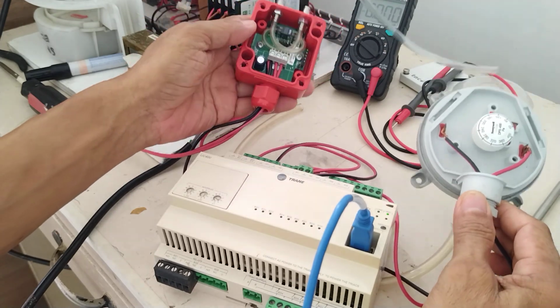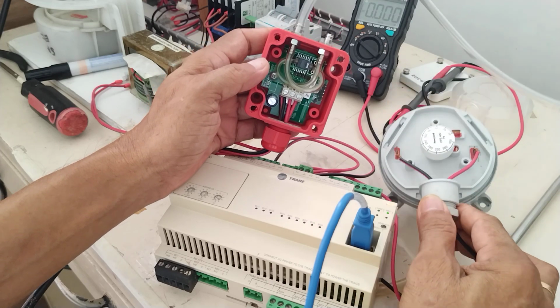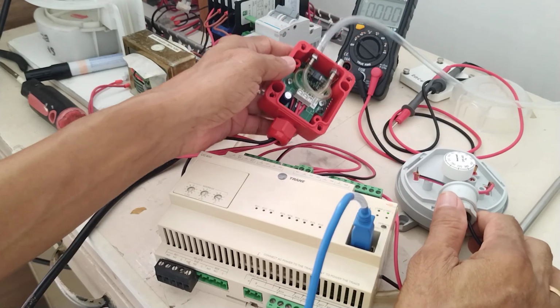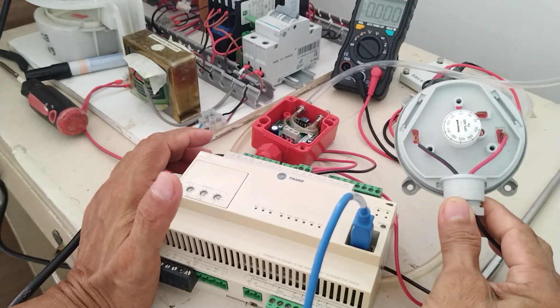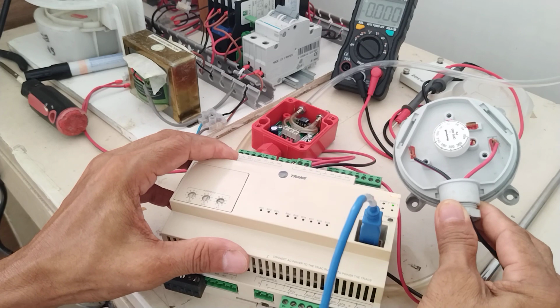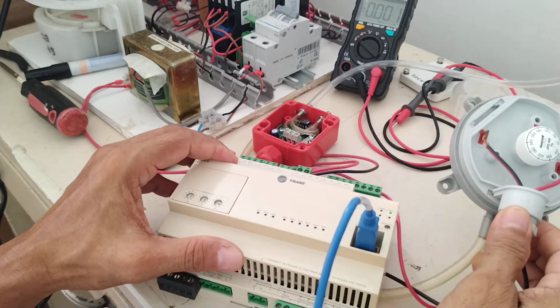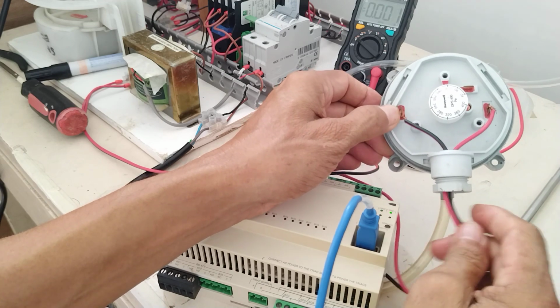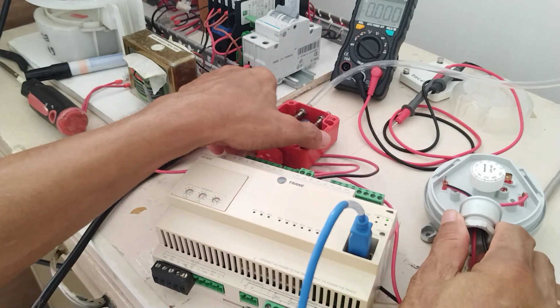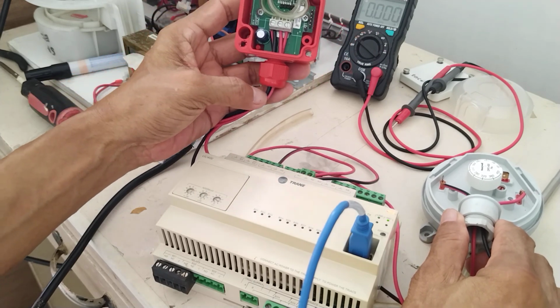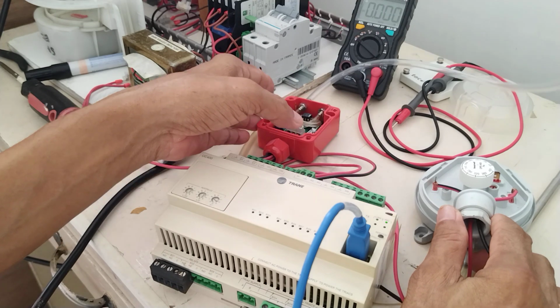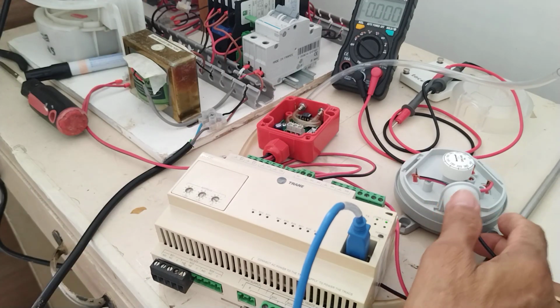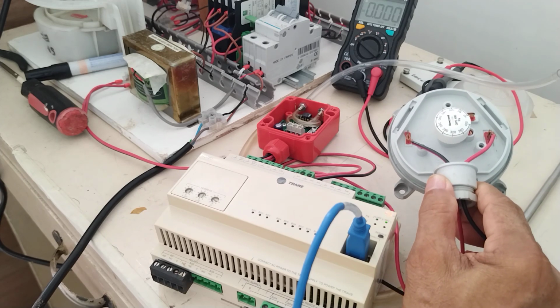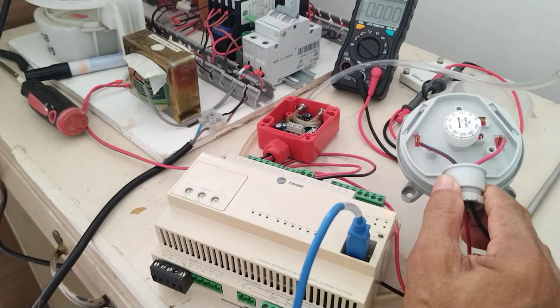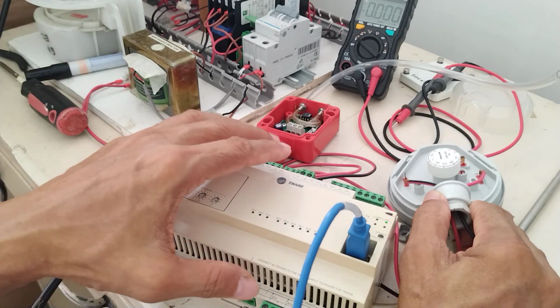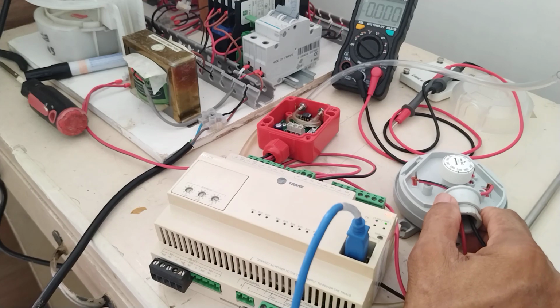Okay. So guys, for the length of the cable, actually, you can use the shop drawing. Let's say this one is installed in a certain area. Then your DDC is located in a certain area. Then your problem is how are you going to calculate the length of the cable? And likewise, you need to check where this one is installed. Then you can check the shop drawing for the equipment. Let's say you are using this in one air handling unit, okay? So basically, the field devices will be installed in the AHU. Then for your controller, there will be one panel.